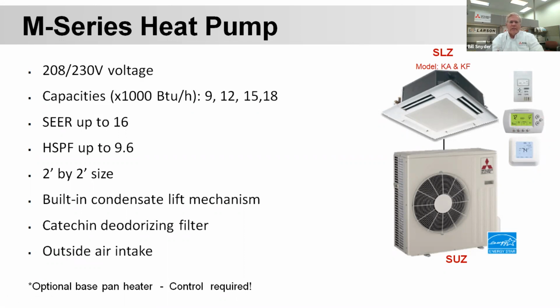They work great, easy to install. Simple. You push a button that says connect, push a button on the thermostat that says connect. They connect together, and you're pretty much done. You can go in and make some adjustments to auto set points and things like that, or you can set timers in here. These do actually do set up and set back. In our climate, I'm not a huge fan of setting back a heat pump, because the heat pumps may not recover if it's below zero. It's going to take a while for that heat pump to actually come up to speed and get the home comfortable.